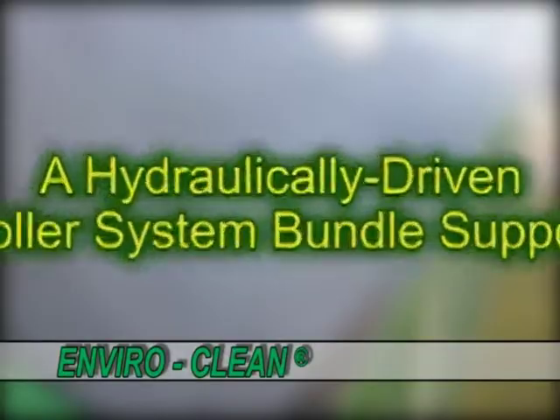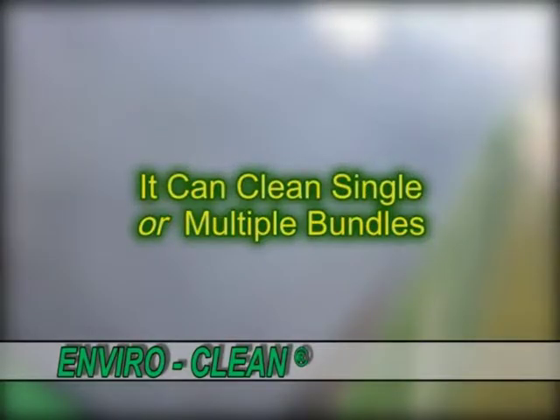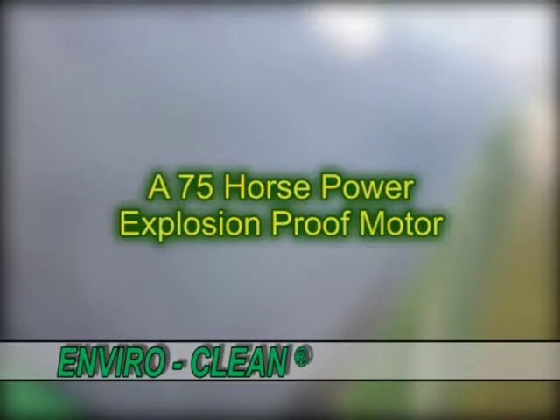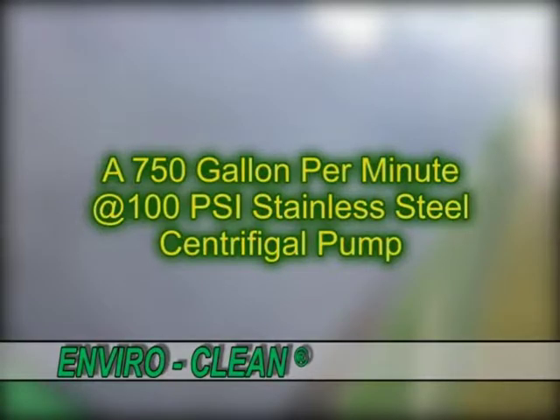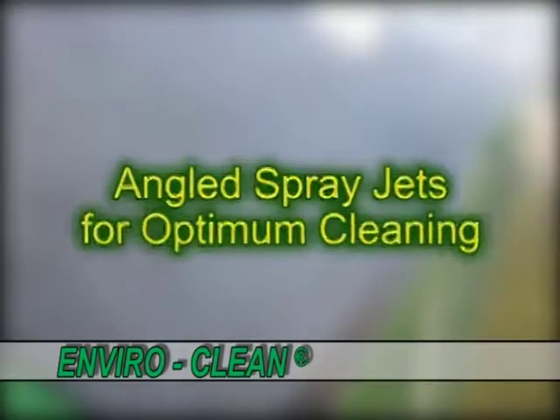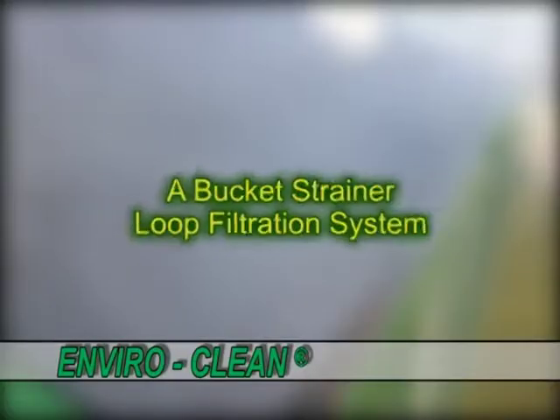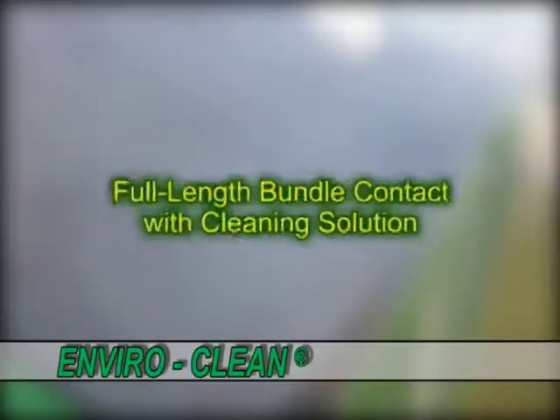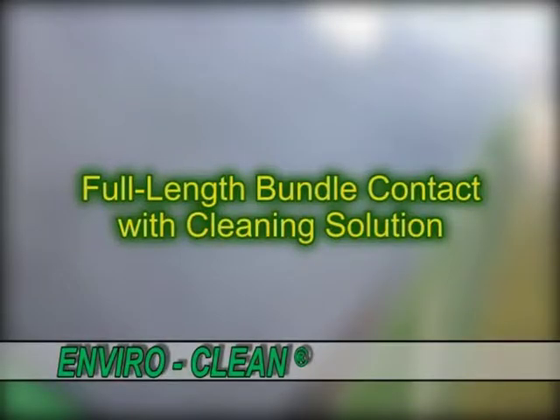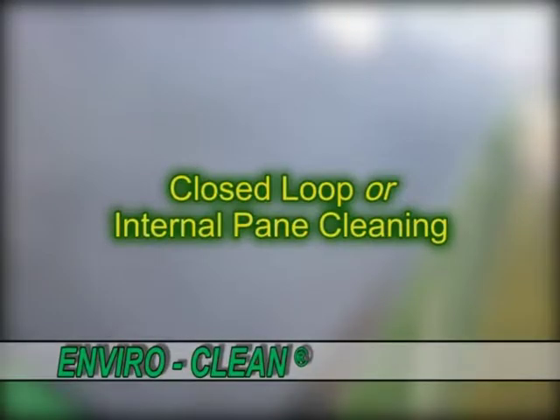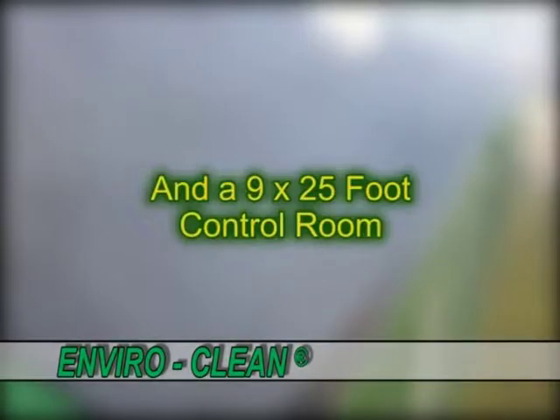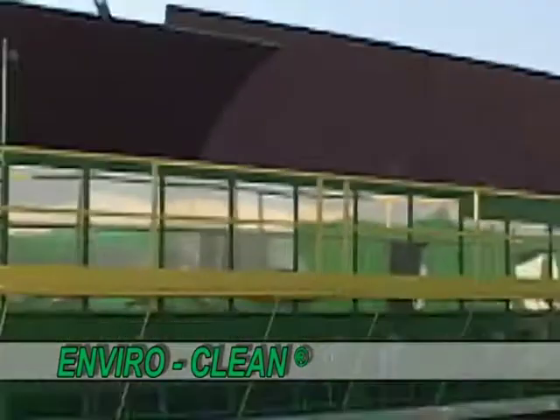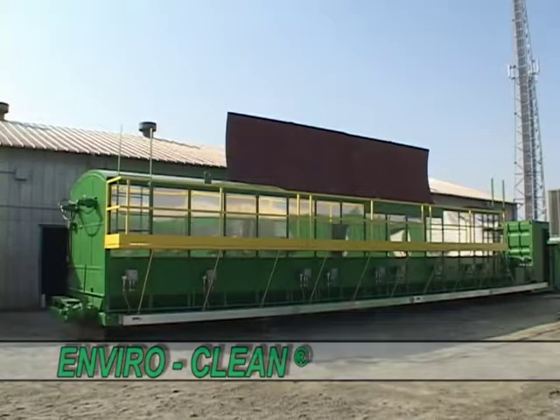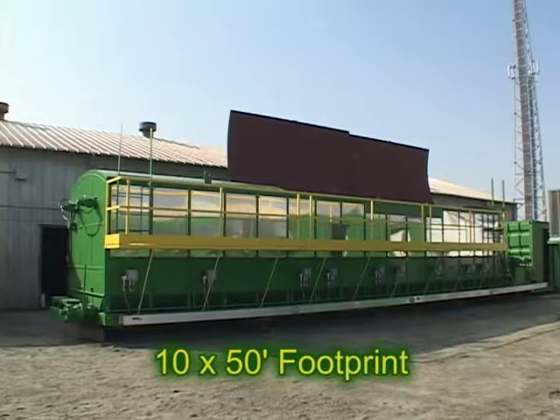The unit features a hydraulically driven roller system bundle support. It can clean single or multiple bundles. A 75 horsepower explosion-proof motor. A 750 gallon per minute and 100 psi stainless steel centrifugal pump. Angled spray jets for optimum cleaning. Temperature-controlled heating vats. A bucket strainer loop filtration system. Full-length bundle contact with cleaning solution as bundle rotates. Closed loop or internal pane cleaning. And a 9 by 25 foot control room. The unit can use customer-supplied heavy hydrocarbon cleaning solutions and has a footprint of 10 by 50 feet.